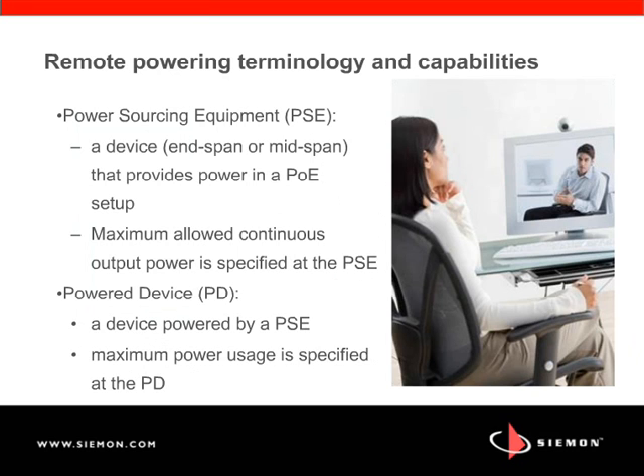and acronyms. The most common acronyms are PSE and PD, and these are used in the specification of the remote powering standard. PSE stands for Power Sourcing Equipment, and that's the device that injects the power into the channel. And the standards specify the maximum continuous output power that's delivered by the PSE. The standards also specify the maximum power that's received by the powered device. As you can imagine, there are some losses across the structured cabling channel. So the performance parameter for output power at the PSE will be slightly different than the power that's available to the PD. And these parameters are important for the specification of remote powering devices.